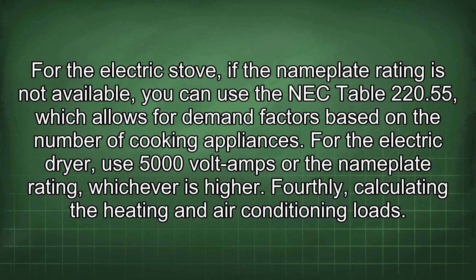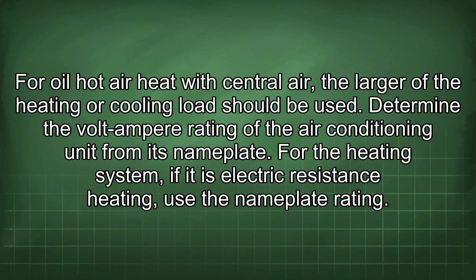Fourthly, calculating the heating and air conditioning loads. For oil hot air heat with central air, the larger of the heating or cooling load should be used. Determine the volt-ampere rating of the air conditioning unit from its nameplate. For the heating system, if it is electric resistance heating, use the nameplate rating. If it is an oil-fired system, the electrical load is usually minimal and can be included with other small loads.